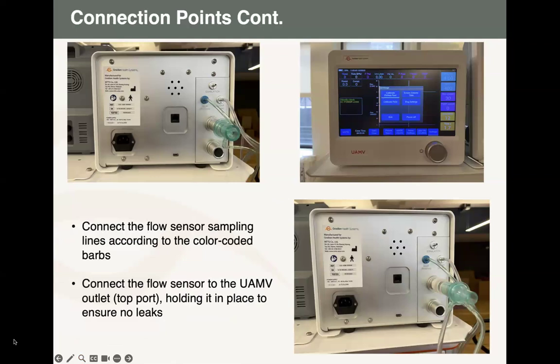Okay, so I'm not sure which machine you have, but I'm sure those who have done machine check with the flow sensor at the back should understand this connection. The emphasis here is that when you're doing the machine check, please connect the flow sensor at the top port. Of course, the other connections, the blue and the clear, stay as they are. But the flow sensor has to be connected at the outlet, the top port. That's where you do the connection for your flow sensor.